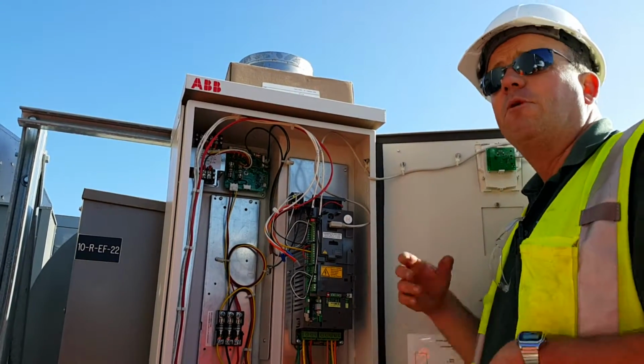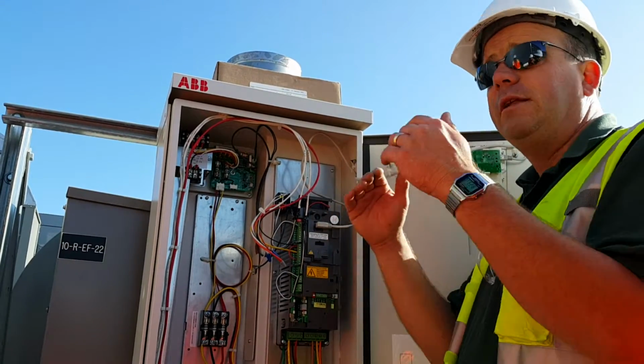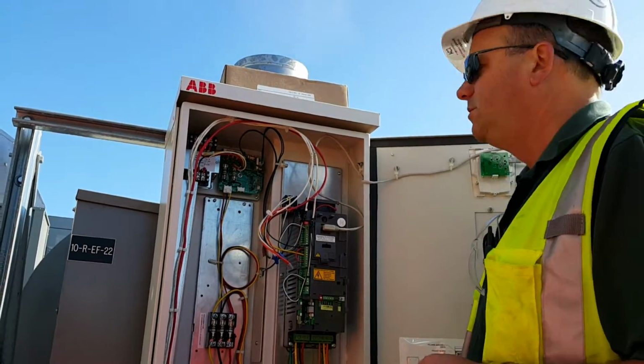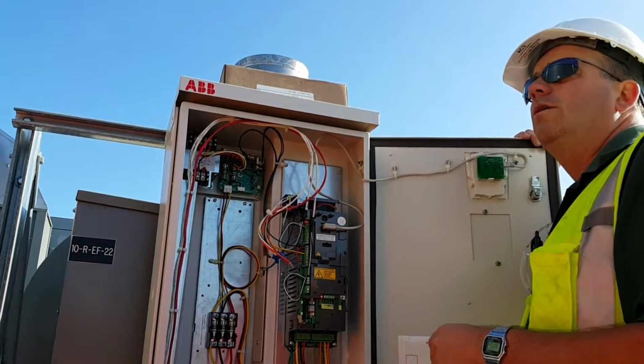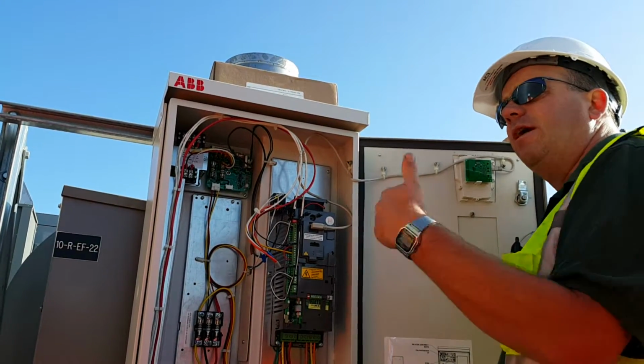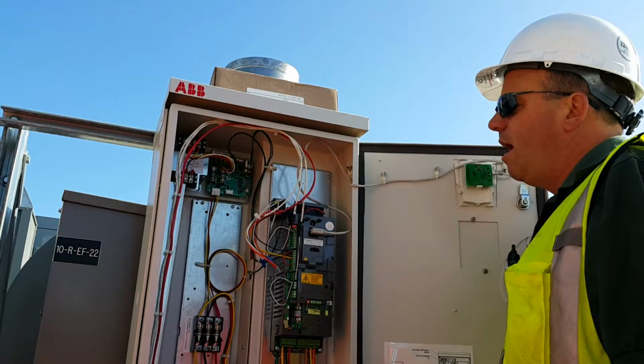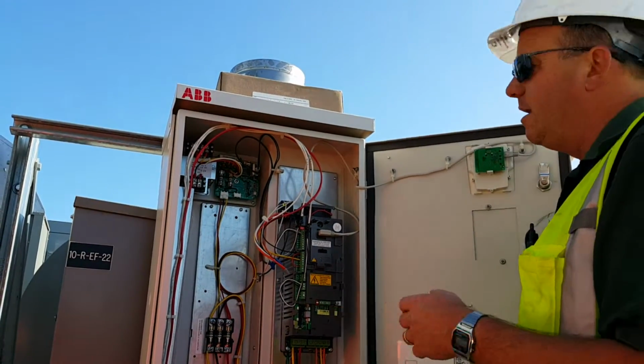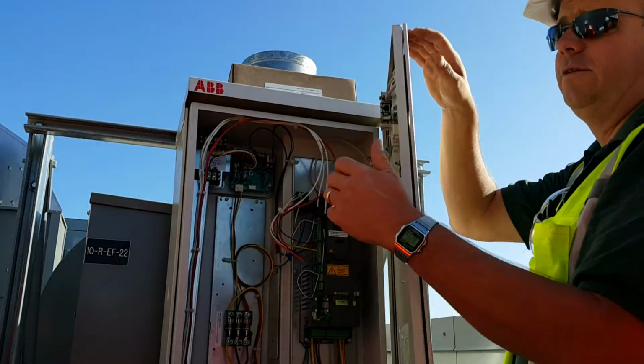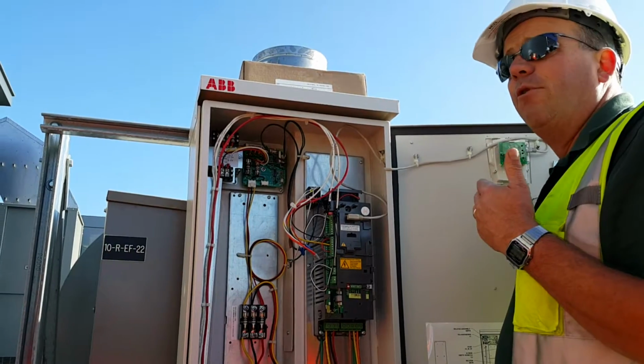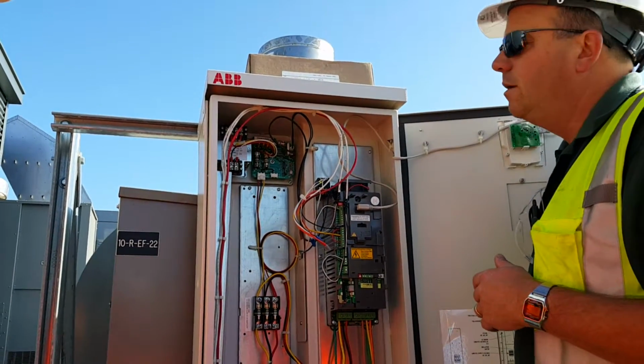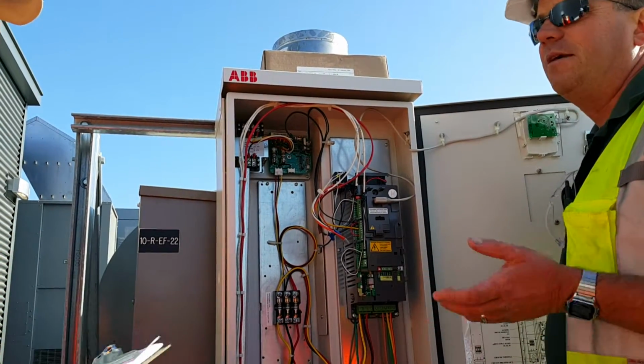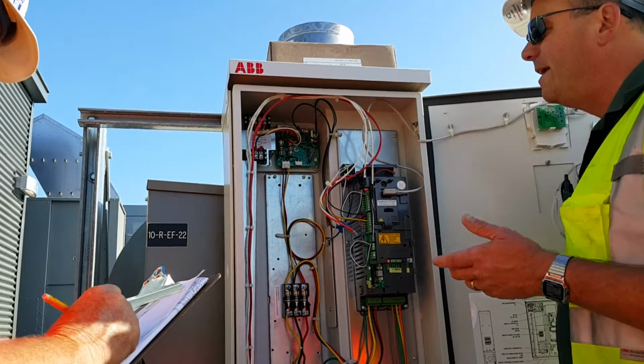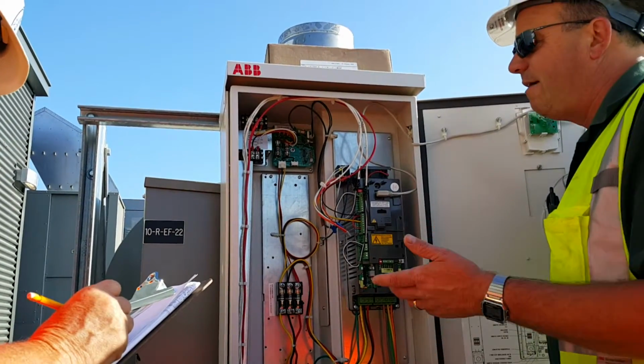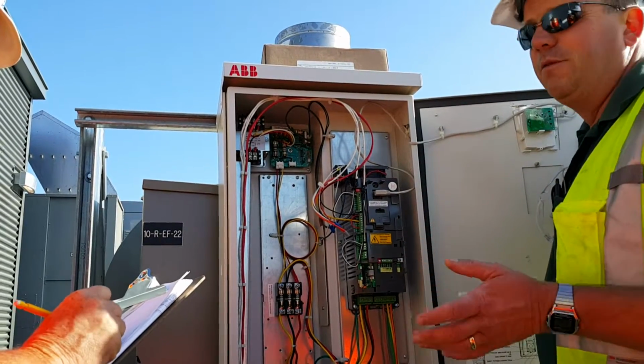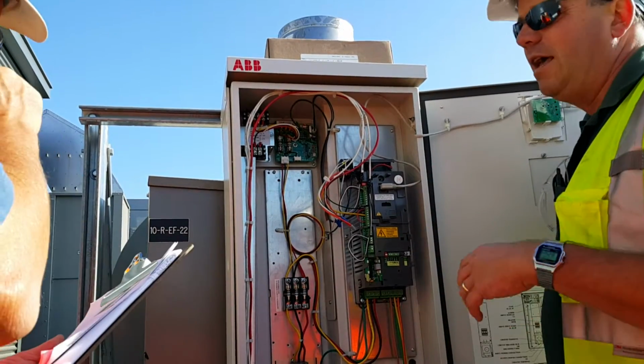So you can use the keypad to transfer memory, but just moving the keypad around doesn't transfer the memory. You have to go into the program, go parameter backup, and load this program. So parameter backup is how you would transfer a program? A program, exactly. Parameter backup, you upload it into the panel, take it to another drive, and download that set in there. Also, when I do a startup, it's not a bad idea. A lot of guys will take these off and mark which one it goes to. Because all these I started up, the last thing I do is I upload a copy of the program into the keypad. A couple reasons. One, if we ever have to change the drive, we don't have to think about it. Put the drive in, drop it in. The other thing is, if somebody comes in, and this happens a lot, comes in after the control guys, they start playing, they have a little bit of knowledge, they start playing with the drive, now nothing works. Over the phone, I can tell them, just go download full set, and they'll say, well, what was wrong?